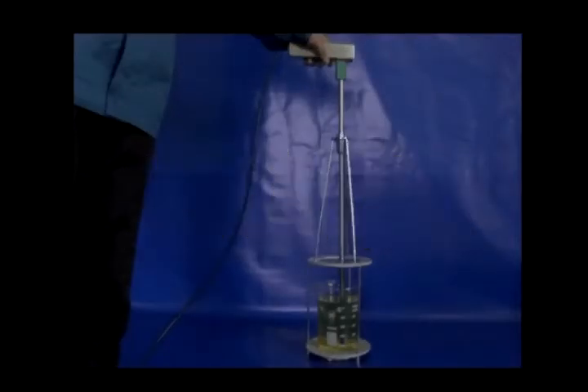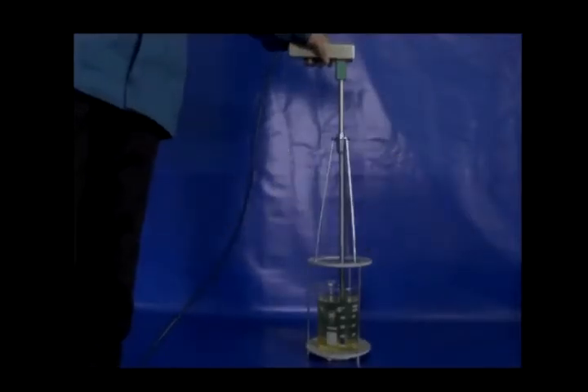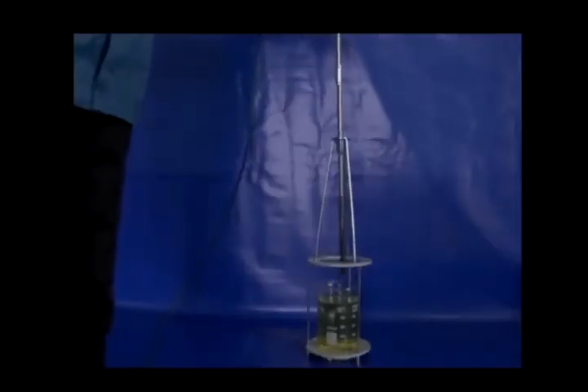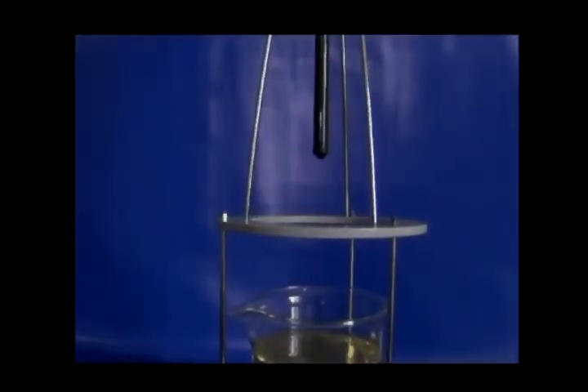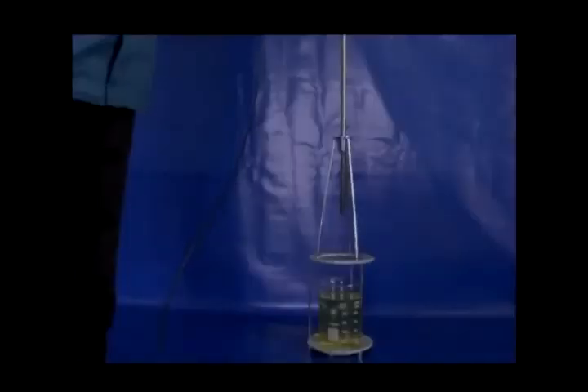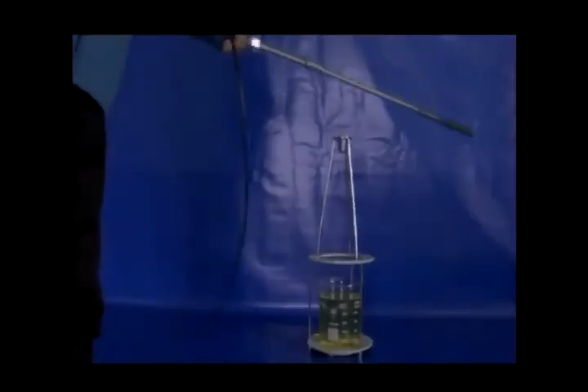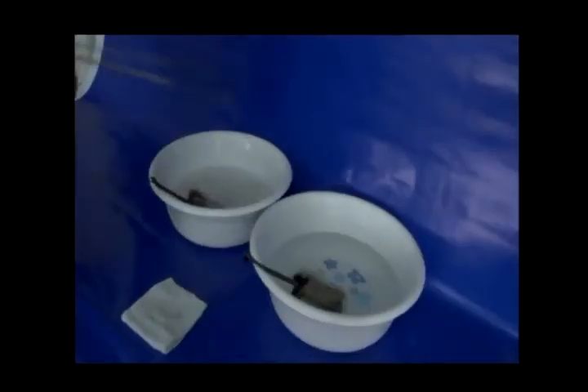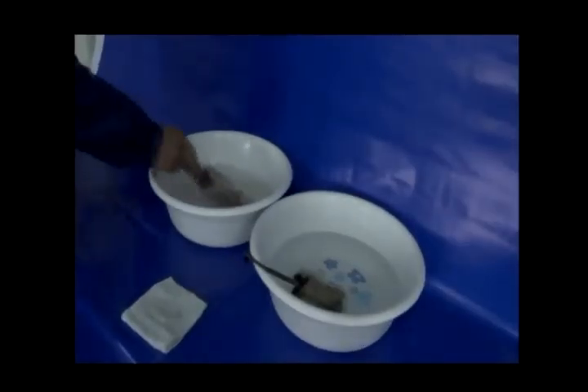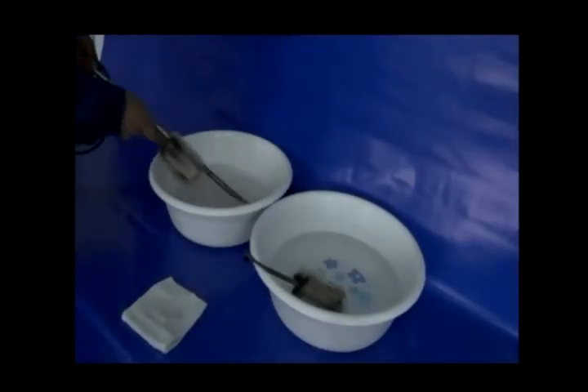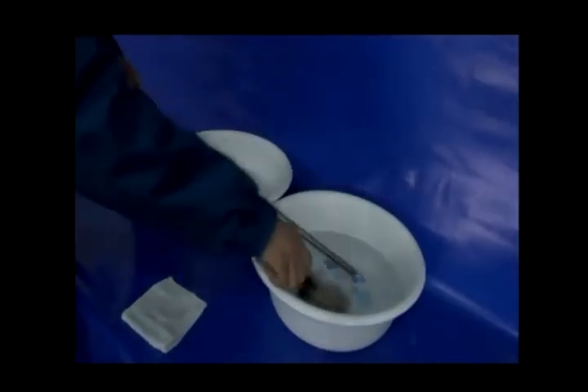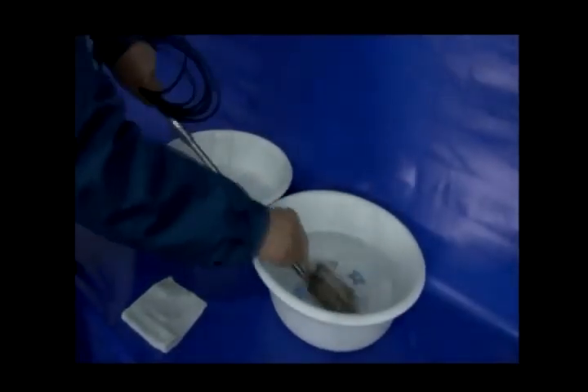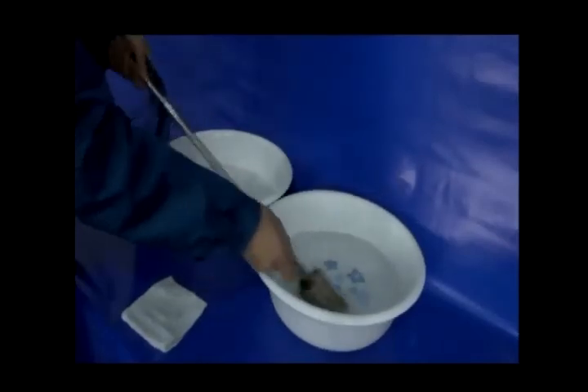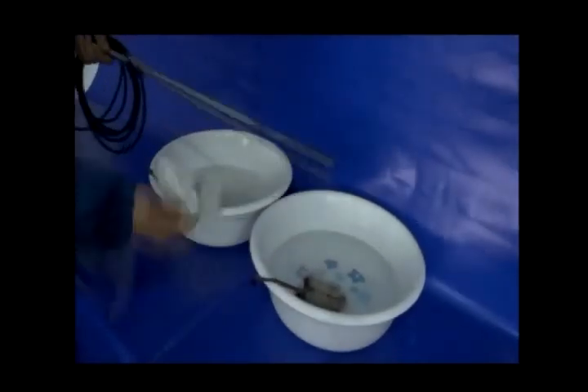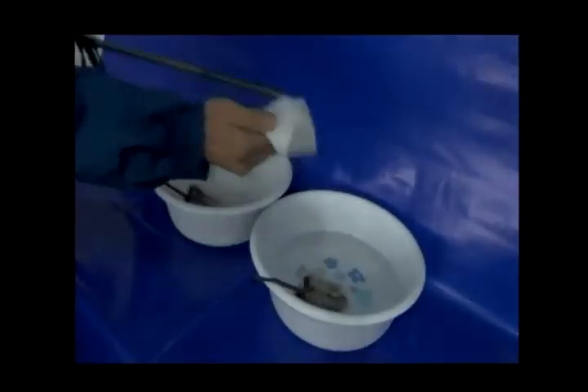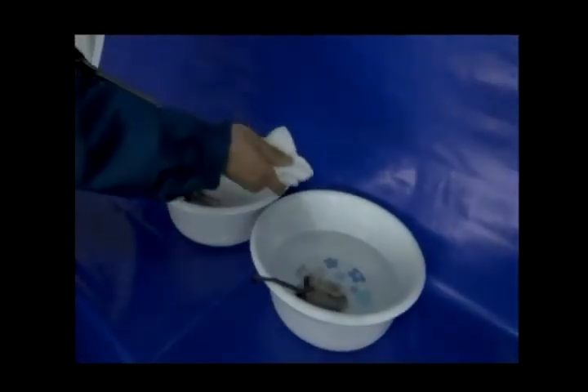Clean the test probe. In order to increase the service life of the probe, and to ensure correct operation of the test probe over a longer period of use, it must be carefully cleaned after each test. First, wash the probe with clean water and scrub it with a mild detergent and a soft brush. At last, wash the probe with clean water again. Dry the moisture on the probe with a clean lint-free cloth. Place it carefully to wait for the next time.